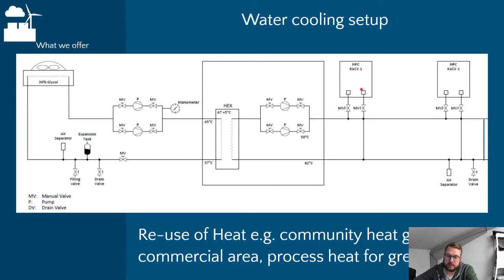The warm water goes out over this valve, and with a return of 62 degrees it goes into the heat exchanger. The heat exchanger's hot side connects to the cooling circuit over the cooling unit, comes back through the pumps and manual valves at about 45 degrees, and goes into the server again at 50 degrees. So this is a warm water cooling setup.